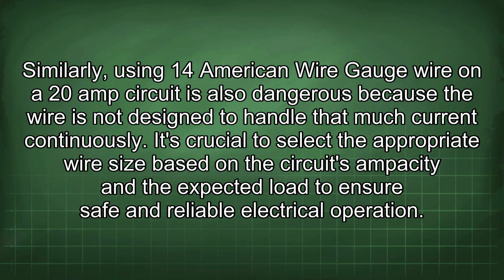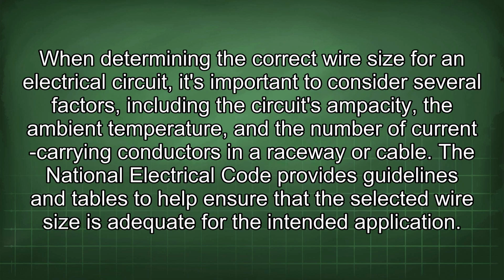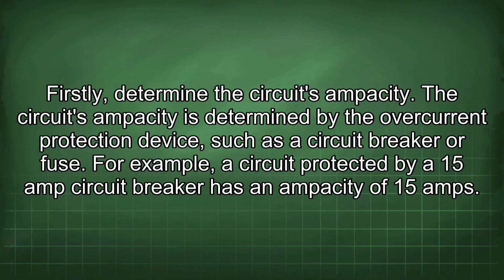When determining the correct wire size for an electrical circuit, it's important to consider several factors, including the circuit's ampacity, the ambient temperature, and the number of current-carrying conductors in a raceway or cable. The National Electrical Code provides guidelines and tables to help ensure that the selected wire size is adequate for the intended application. Firstly, determine the circuit's ampacity.